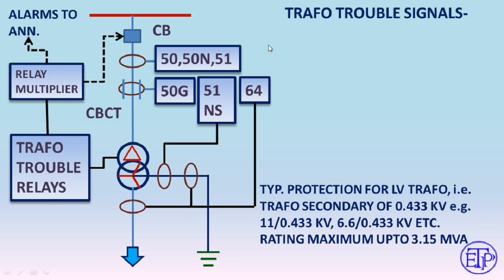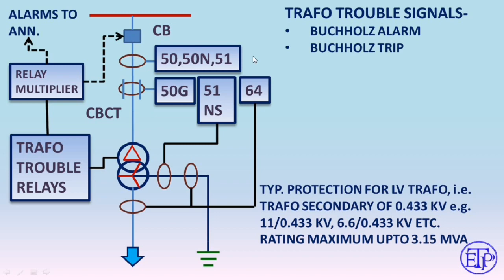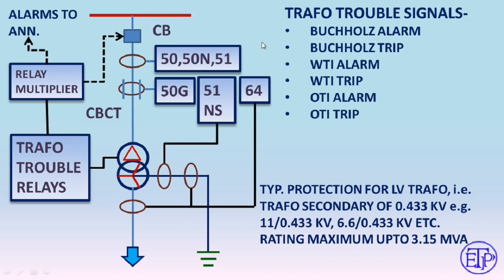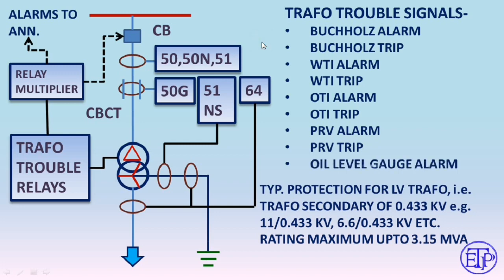The transformer trouble signals are: Buchholz alarm and Buchholz trip — generated by the Buchholz relay. Up to a certain level of gas generation, Buchholz alarm goes to the annunciator; above the setpoint it trips the transformer feeder. Then there is WTI alarm, WTI trip, OTI alarm, OTI trip, PRV alarm, PRV trip, and oil level gauge alarm. These are the most common transformer trouble signals exchanged with the transformer feeder.